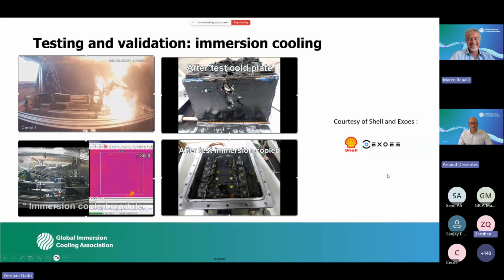Wow. So this was with a cold plate. No worries. So you see, and before we move to the video, thanks, Zishan, you see here that at the top of the slide, you have a cold plate configuration, and you see the test results after the nail penetration with cold plate. You have all the cells that burnt, and it's not only a fire that you have, it's between the fire and an explosion. And you will see in the video that we performed with Shell liquid that with immersion cooling, we have no thermal runaway propagation. So you have soot, that's why it's black, but you see black mass, which comes from the cell that has been abused. But you have only soot and black mass here, but the other cells are completely running after the test, which is a great performance. So now, thank you, Zishan. We can move to the video.